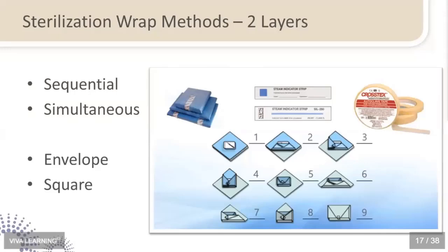I will mention that if you are buying single layer wrap, the best practice recommendation from AAMI ST79 is, if you are not using a bonded wrap, sequential wrapping is recommended. So don't try to just put those 2 pieces one on top of the other and do a simultaneous wrap. Best practice, sequential wrap for using 2 separate single layers. You have choices as far as the design of the wrap that you use. In dentistry, most commonly, we are seeing the envelope method used, and that's the diagram that you see there. Envelope or diagonal method, sometimes it's called.